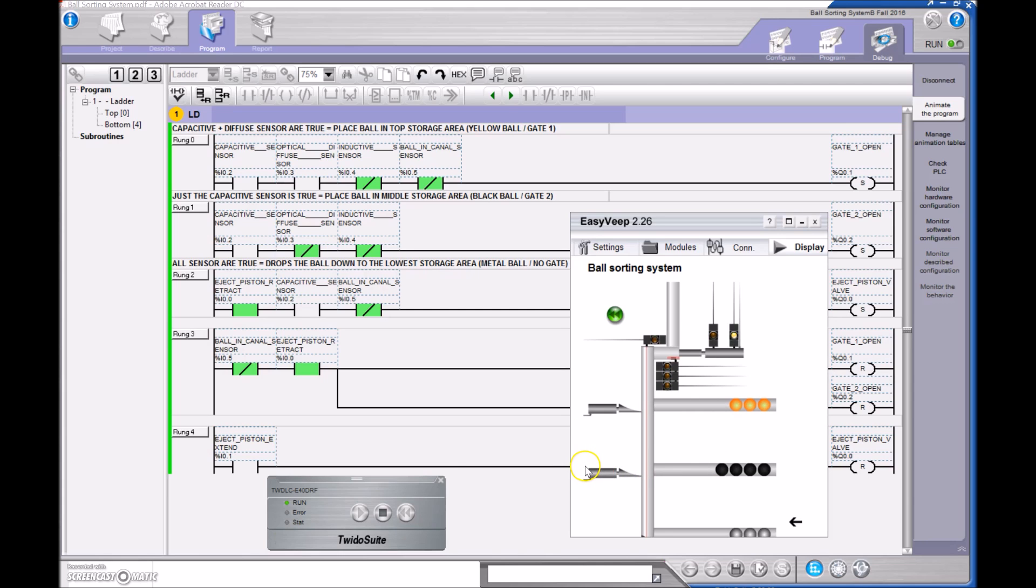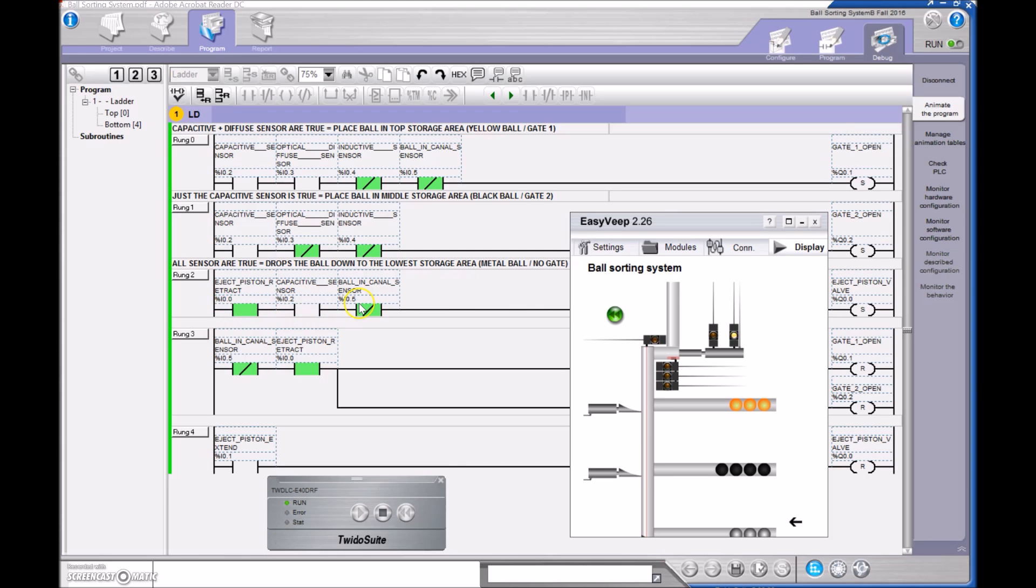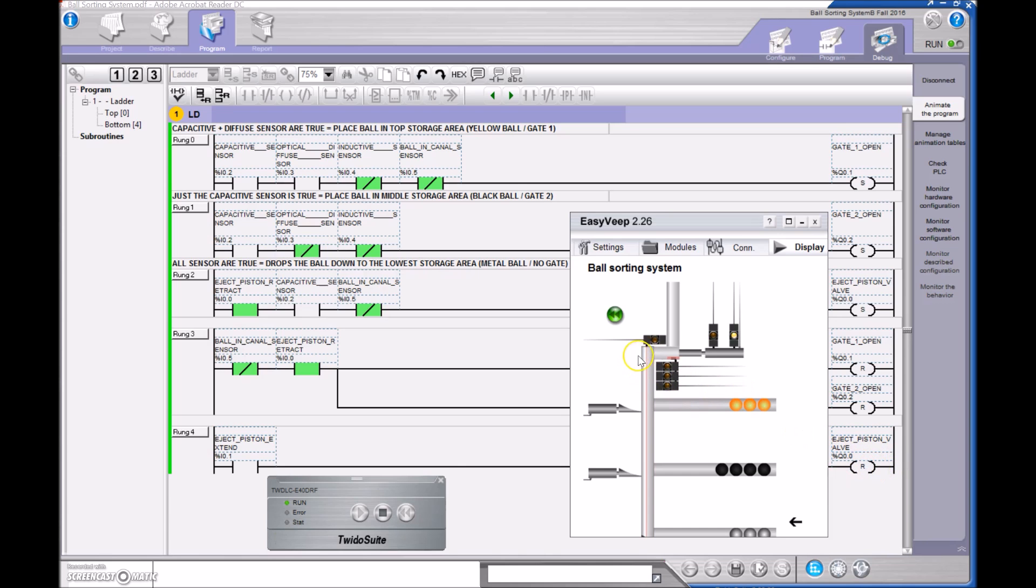Finally, I need a way to make this guy just extend and retract, extend and retract, if there's a ball here. And that is going to happen in that my extension is going to happen right here. So if there's a capacitive sensor, there's nothing in this column right here, and the eject piston is in the retract position, then I'm latching on this guy, so that's going to push the ball out. And then to reset that latch and make this go back, all I'm just saying is once it has extended and tripped off the sensor, then I want it to come right back. So I'm going to take away the latching portion of that circuit.